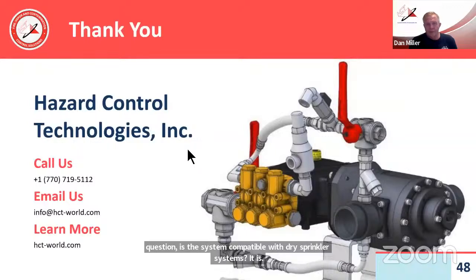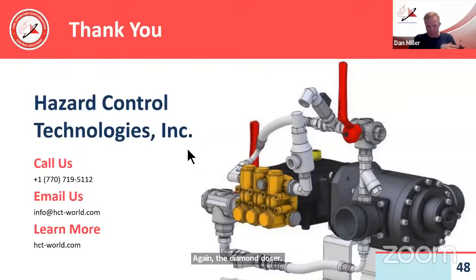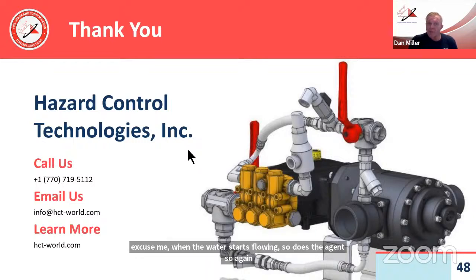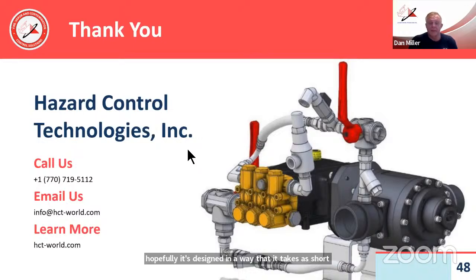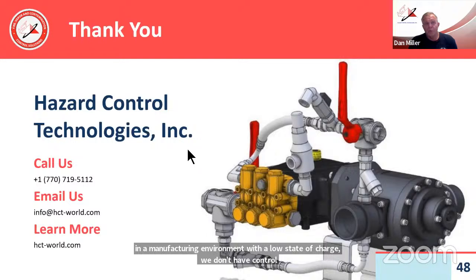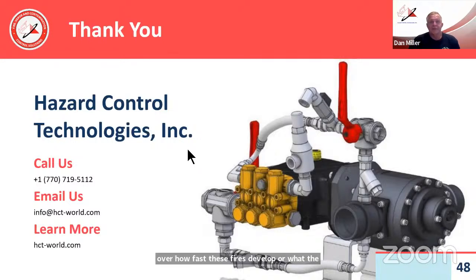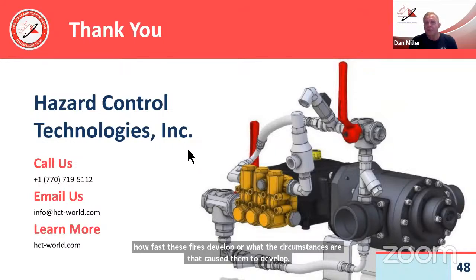Again, the Diamond Doser is just placed in the riser room that's climate controlled. And when the water starts flowing, so does the agent. So again, hopefully it's designed in a way that it takes as short a time as possible to get to the deluge heads. That delay in a large system could be significant. You need to make sure that it's short. Fires in EVs and lithium ion batteries do develop very, very quickly when they want to, and we don't have control over that. Even in a manufacturing environment with a low state of charge, we don't have control over how fast these fires develop or what the circumstances are that cause them to develop. But the Diamond Doser is compatible with dry sprinkler systems.